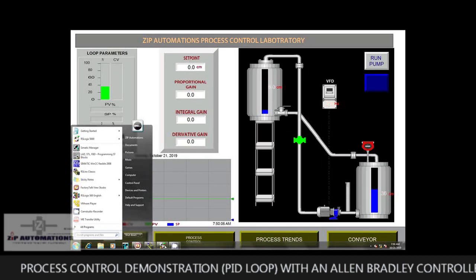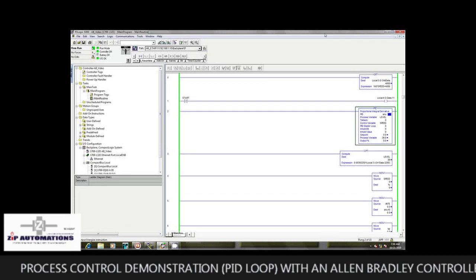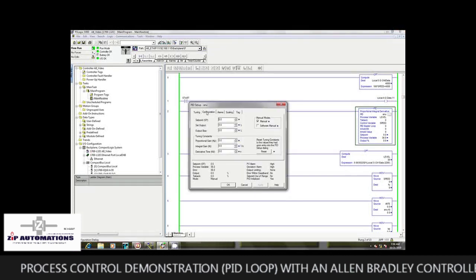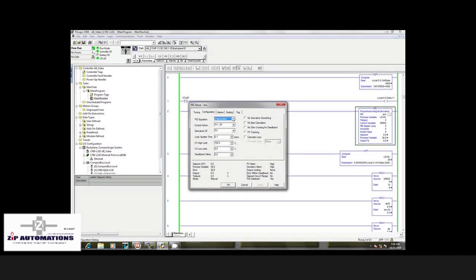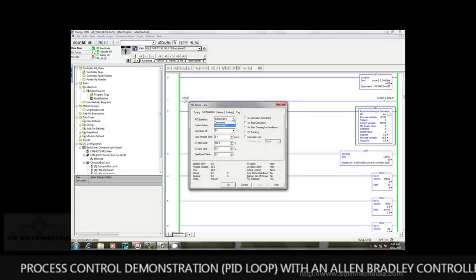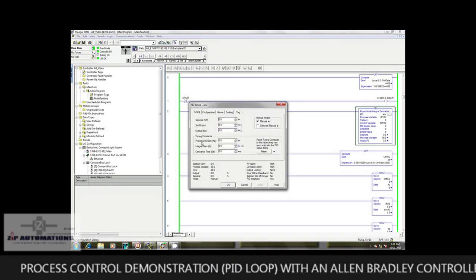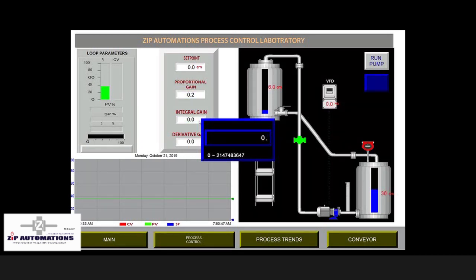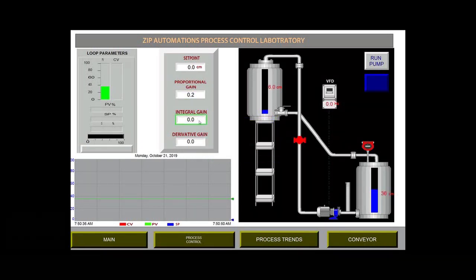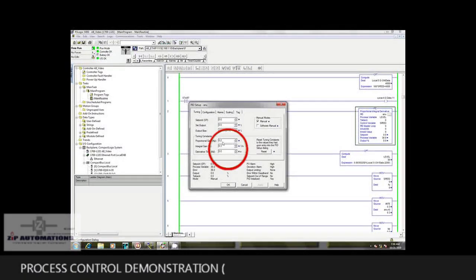I'll be showing you what our program looks like. This is RSLogix 5000 software, and this is our PID block. Here we have the tuning parameters. For this demonstration we are going to be using the independent PID loop, and I'll be explaining what that means later. Here we have the proportional gain, the integral gain, and the derivative time. I'll be inputting the values from our FactoryTalk control screen. For the proportional gain I'll be inputting 0.2, and for the integral gain I'll be inputting 0.3. In our program we can see that the values are reflected here.